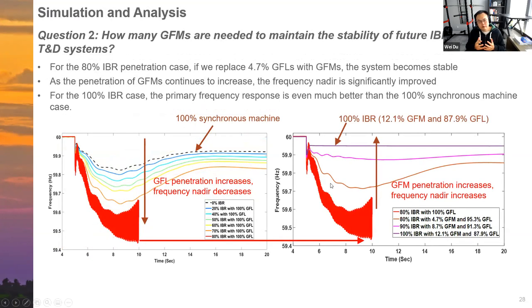And we know grid forming inverters are important. So the second question is: how many grid forming inverters are needed to maintain the stability of a future inverter dominated system? Starting from this 80% case, we start to replace some grid following inverters with grid forming. Once we have more and more grid forming inverters in the system, the primary frequency response is significantly improved. If we go to the 100% IBR case, that means we replace all the synchronous machines with grid forming inverters, and the system has about 12% grid forming inverters and 88% grid following inverters.